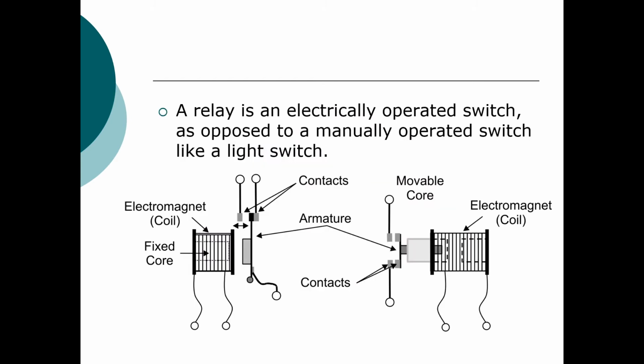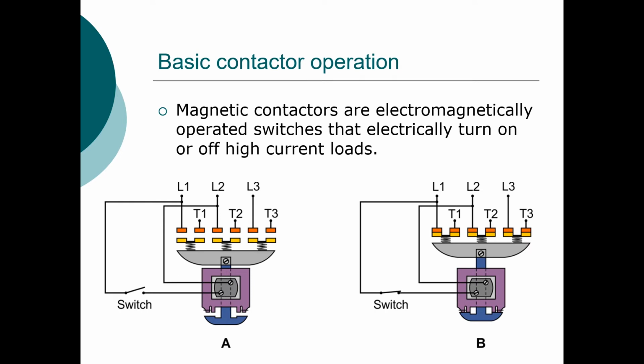Every relay has a coil and a core. However, the core can be either fixed or movable depending on the usage. Fixed core relays are typically smaller plug-in types, where movable core relays are more for industrial usage. The moving part of the relay, whether it is the core or the contacts, is called the armature, and the purpose of the armature is to change the state of the contacts, so normally open contacts will close and normally closed contacts will open.